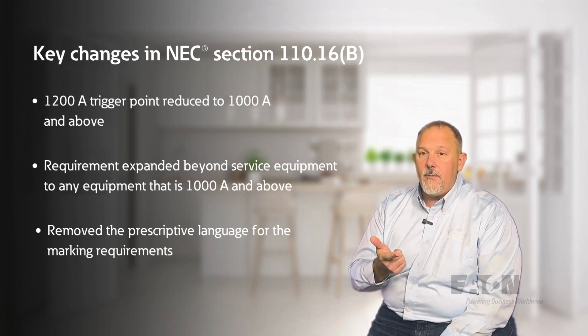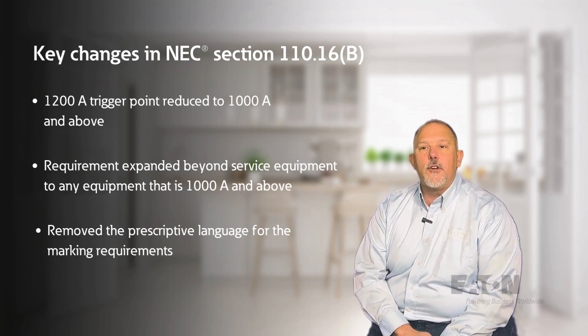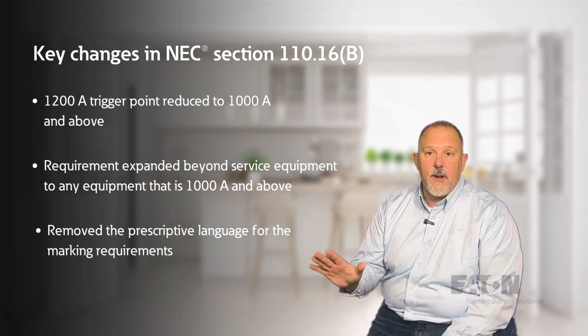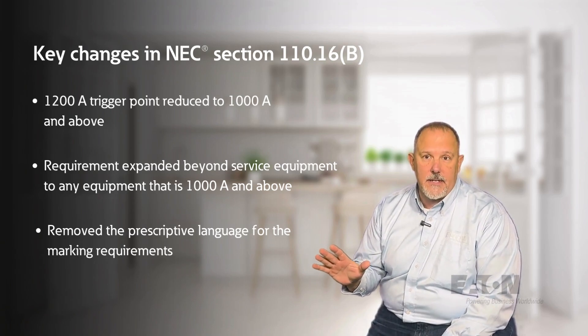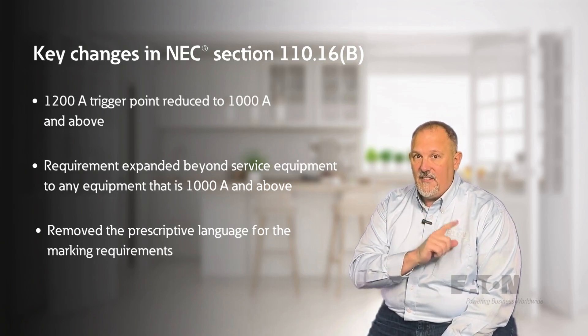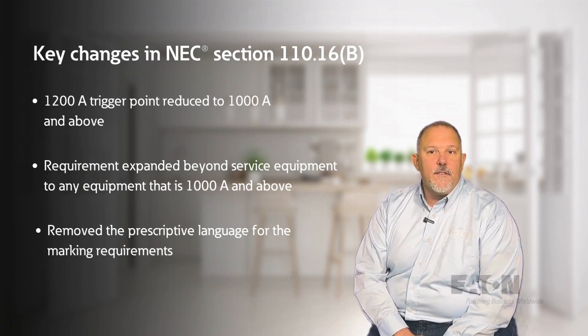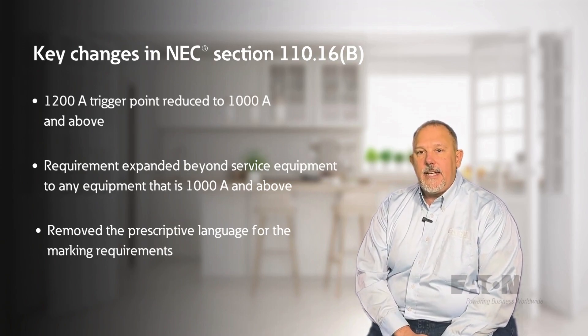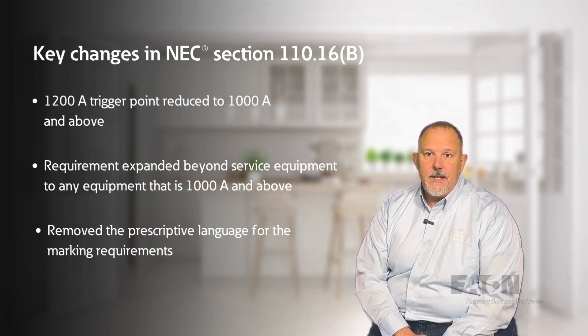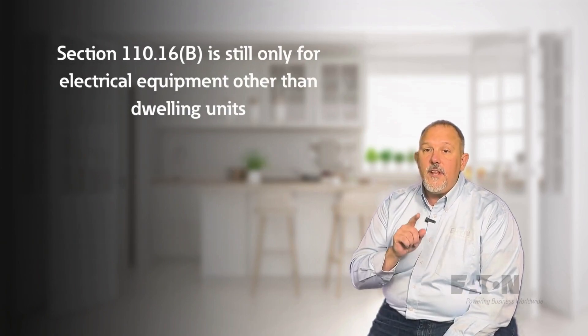The third change removed the prescriptive language for the marking requirements, which included the voltage, available fault current, and clearing time of the service overcurrent protective device, to simply reference industry practice — what we know as NFPA 70E. You'll find the reference to NFPA 70E in an informational note.